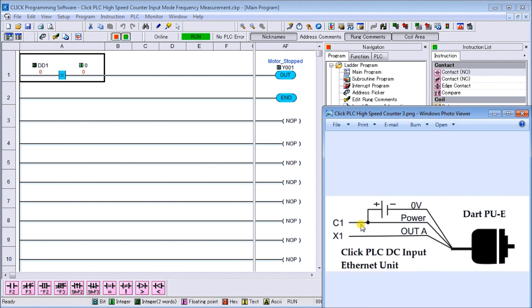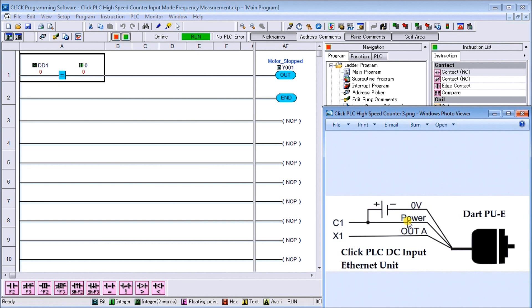So that means our common sits at plus 24 volt, the other side will go to our black wire of our dart, then the power wire will go to our plus 24 volt, and then our output white wire from the dart will go to X1 which is our first input. So that is our wiring diagram.